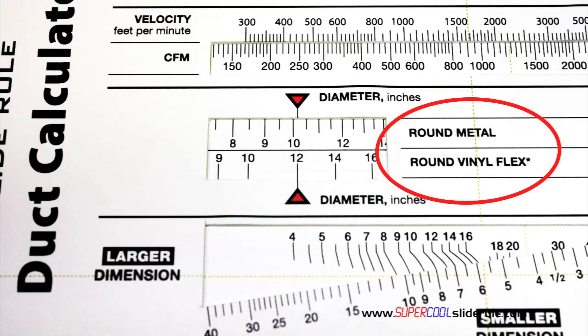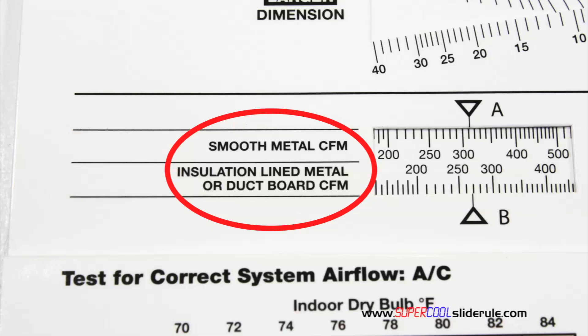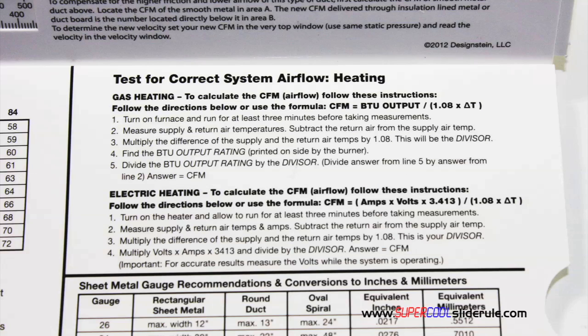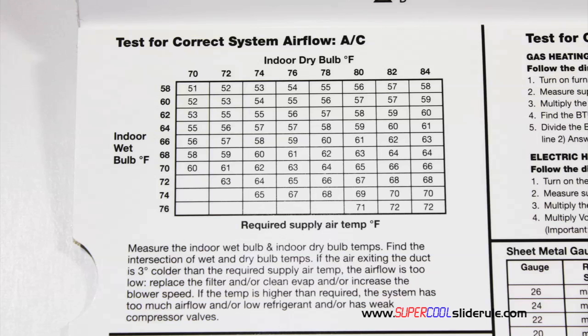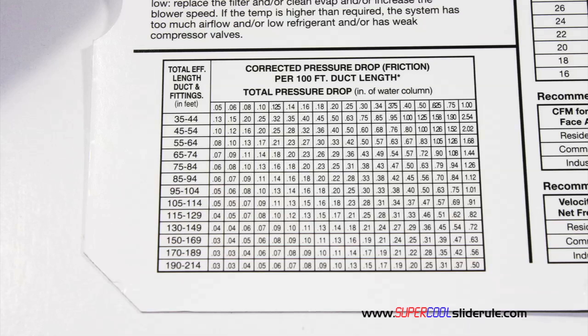Inside is packed with even more information. It performs sizing of both metal and flexible duct. It has the only direct reading conversion from smooth metal to insulation-lined metal we have ever seen. The majority of technicians have never been taught that if the insulation is on the inside of the ductwork, you cannot size it with a regular duct calculator. It has step-by-step directions for determining airflow through a gas furnace, electric furnace, or an air conditioning unit, as well as pressure drop multipliers for ductwork and recommended velocities.